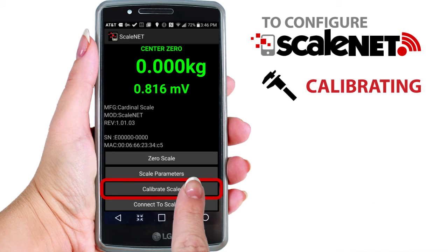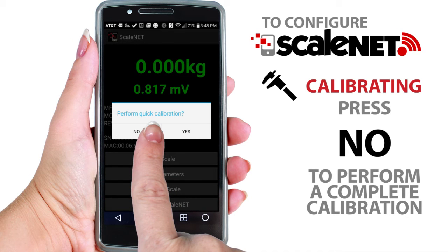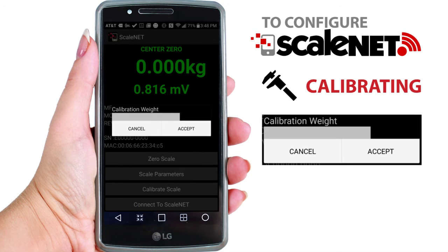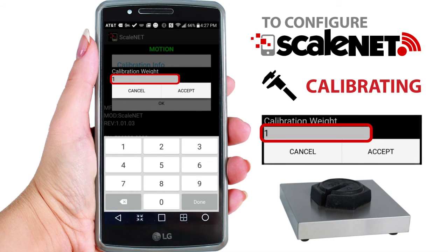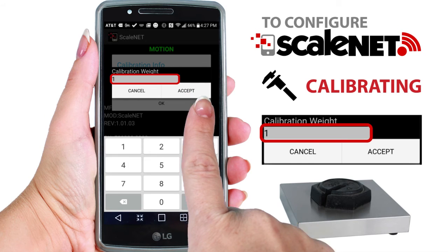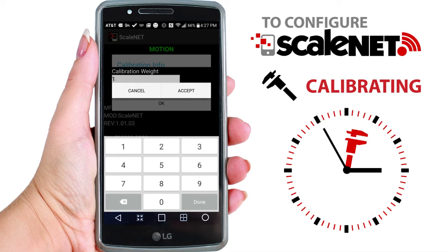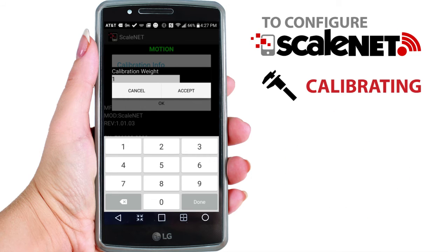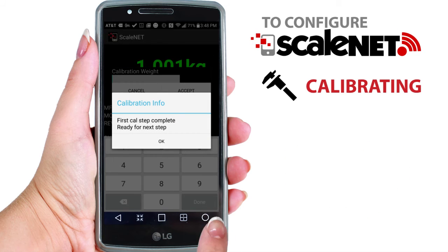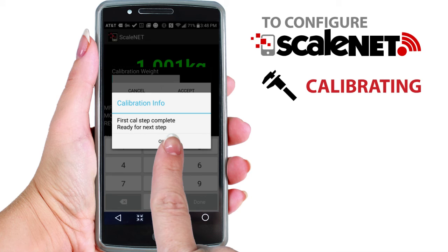Begin by pressing the Calibrate ScaleNet button. The utility will prompt for the weight on the scale in a dialog box. Enter the amount of the test weight, making sure that the test weight is seated on the scale before selecting OK to begin the calibration. This dialog box will remain after clicking OK for approximately 10 seconds while the ScaleNet module is performing the calibration. Once it has disappeared, you will see a pop-up message indicating that the first calibration step is complete.